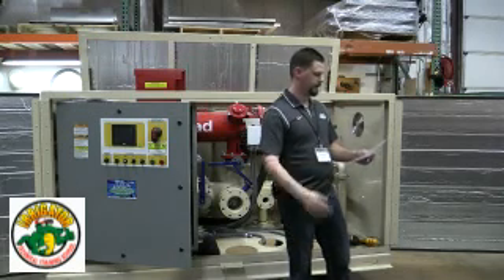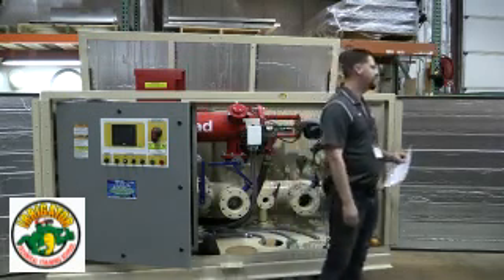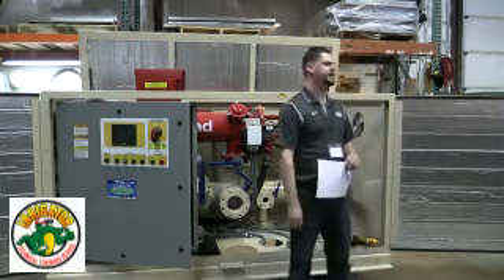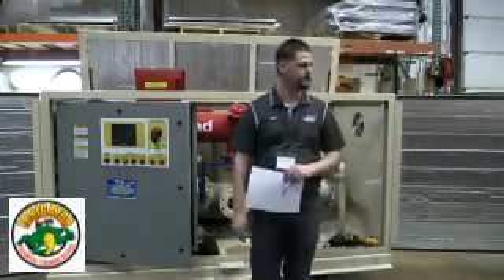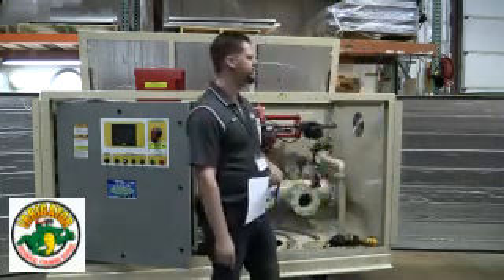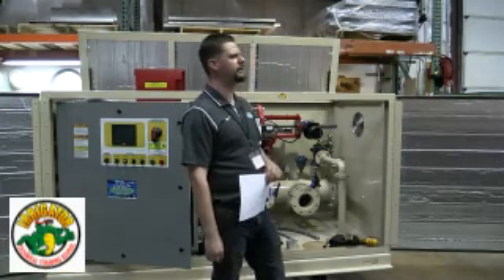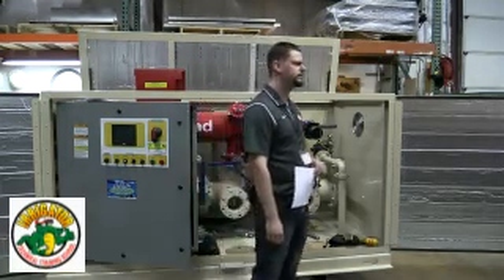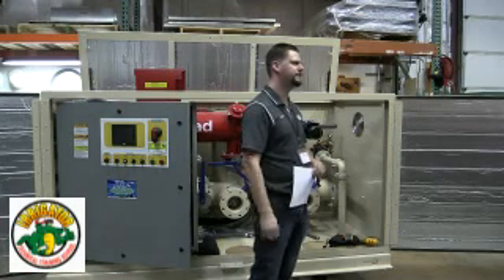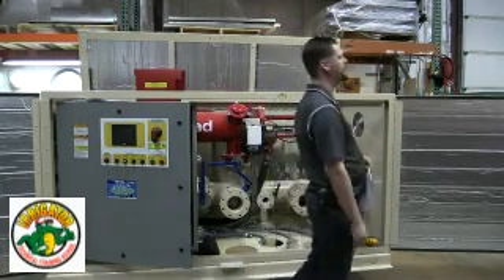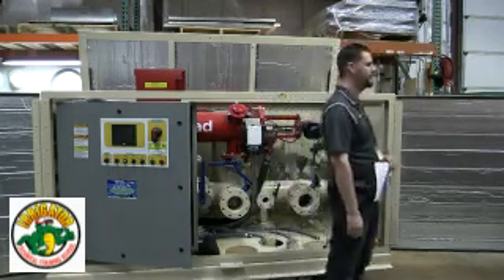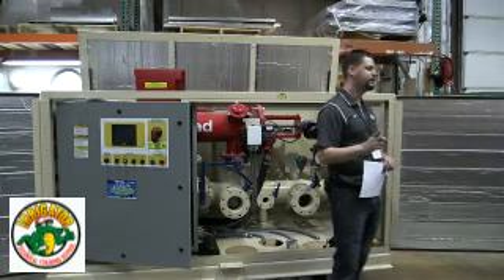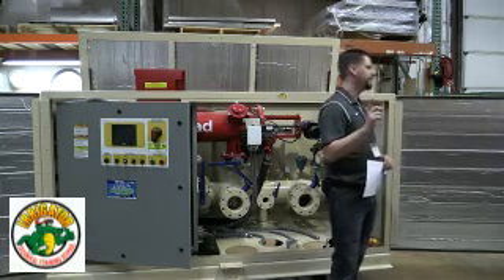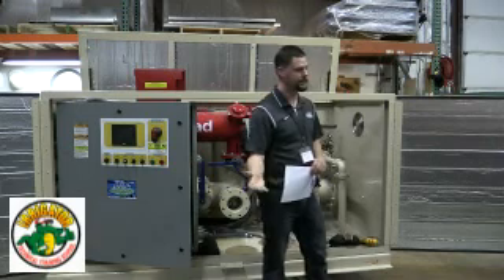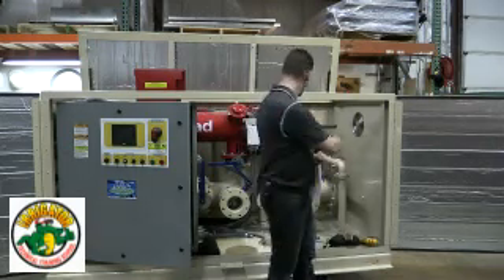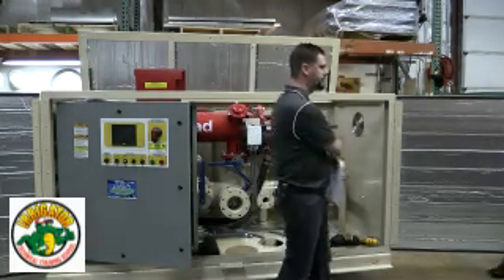Oh, here's one. Always get calls. My drive keeps tripping on device over temp. Well, does it run for a little bit before it trips? Yeah, it'll run for 10 minutes or so, and it'll trip every single time on device over temp. Say, well, I'd be happy to come out and fix that for you. However, there's one thing I'd like you to do.